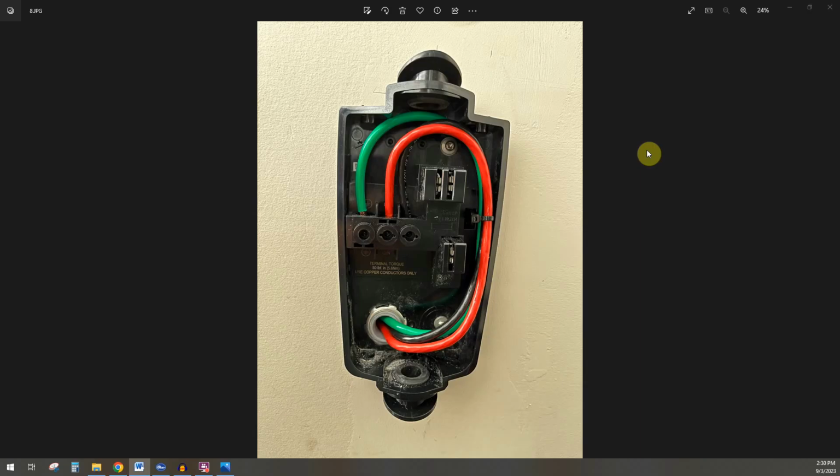When you're ready to get your wiring all set up, make sure you wire the load side first. That's going to be, in this case, the wire box. So wire this side up first and then do the breaker side. The reason is you don't want to put in your breaker, even though it's off, and maybe there's something wrong with it, or you forget to turn off your panel, and you accidentally energize your breaker even though you think it's off, and then you start working on the load side and shock yourself. By doing the load side first, you can't do that, because there's no power on the line side, your breaker side, to even be able to do that. So normally you want to start with the load side first.